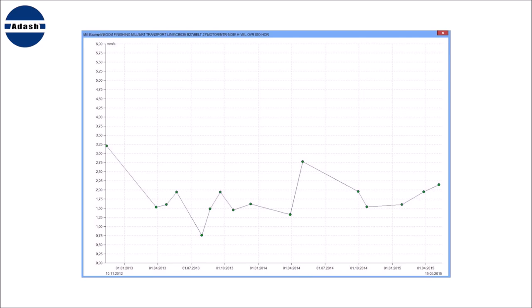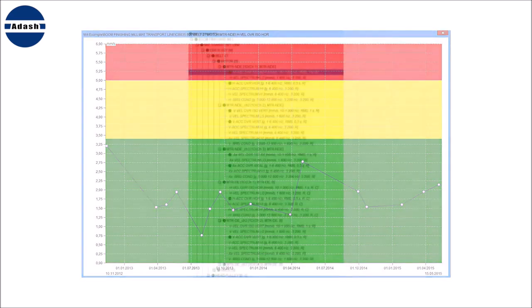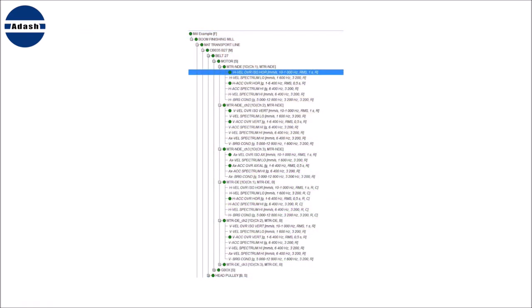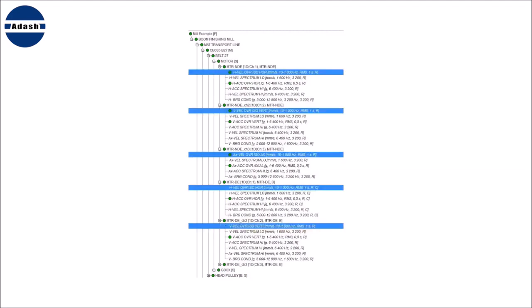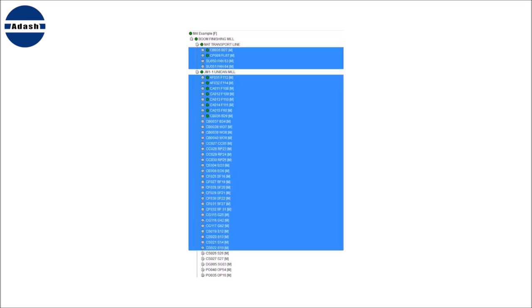The statistical alarms generation works with all measured values or readings from the past. The statistical process finds normal values and offers alarm limits to you. You can apply the limits by statistics for one point, for many points together, or for a group of machines if they are the same or very similar type. You can select all required items and all data from them will be used.